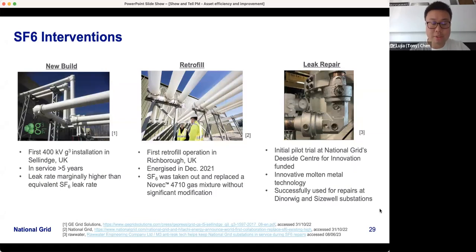The one in the middle is some of the research initiated at Manchester, looking at developing a retrofill solution. Like the name suggests, this is to take the SF6 out of existing legacy equipment and replace it with a more environmentally friendly alternative with significantly lower environmental impact. We found a solution, an optimized solution, that can give up to 99% reduction in the equivalent carbon footprint, basically without modifying the rated pressure or having to open the equipment.